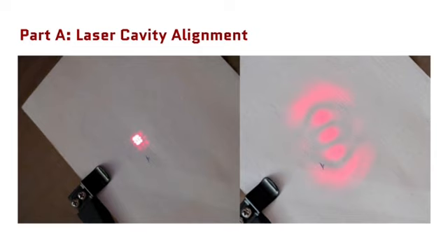the laser cavity. We started with a pre-aligned green laser where the gas tube was adjusted using the tip and tilt until the green light filled the tube and passed through to the iris. The system would then be adjusted without the tube to retroreflect the laser using a mirror. Then the gas tube would return and a HeNe would replace the green laser to finish alignment of the cavity.